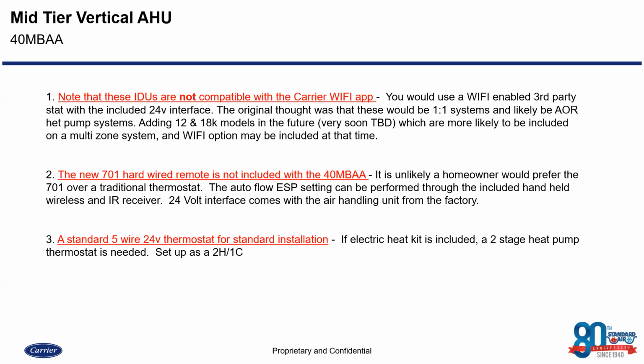So when we are setting up our third-party thermostat, it's important to note that we need a standard 5-wire 24-volt thermostat for installation. So for example, if we had a system with no electric heat, we would need to set that thermostat up as a 1 heat, 1 cool option, and not a heat pump, because we're not going to use the O terminal. Okay, the W1 is what sends the control signal to the interface to be able to tell the system that it has a call for heat.